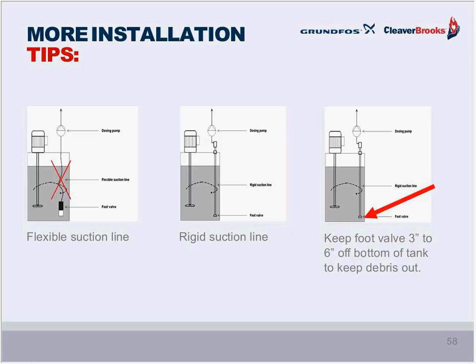And use a rigid suction line rather than a flexible one in your chemical tank if a mixer is installed, so the suction line does not get tangled with that mixing blade. It kind of sounds like common sense once you read it. But yeah, the flexible suction line can get sucked into the vortex and then wrapped up across that shaft. Also leave some clearance from the foot valve to the tank bottom to avoid sucking in sediments that made their way to the bottom of that chemical tank, which could cause the valve, and later the dosing pump, to get blocked, which would cause your pump to stop moving fluid.